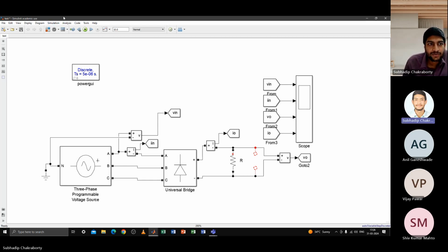Likewise you need to do, and also check what type of filters you are connecting. Check whether it is a high pass filter or a single tuned filter. You need to know the circuits. Otherwise, although the quality factor and all those things will be given, you need to know at least how they look. From that you can calculate one by one. First, if they don't want reactive power compensation, then you just calculate for the harmonic components, and then you proceed with the quality factor to find the value of the resistors. So that is how you should do it.